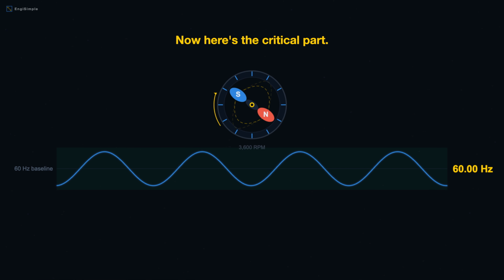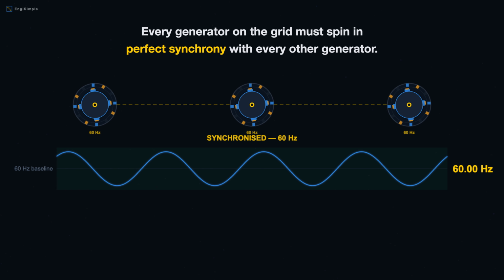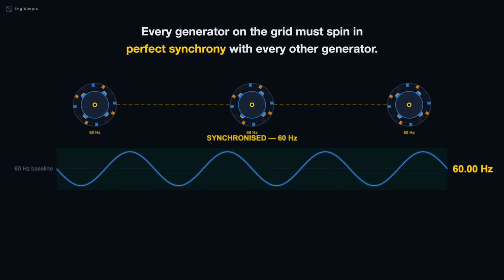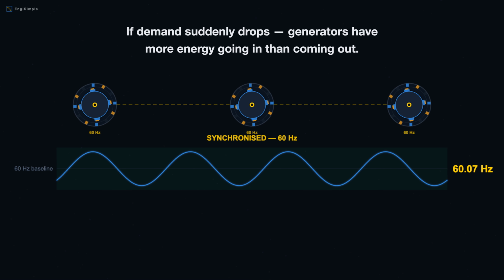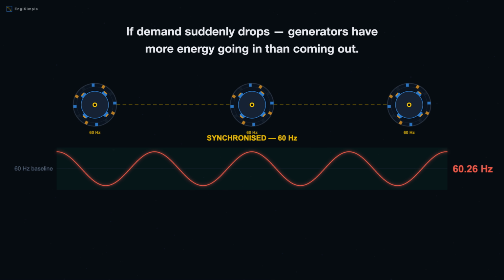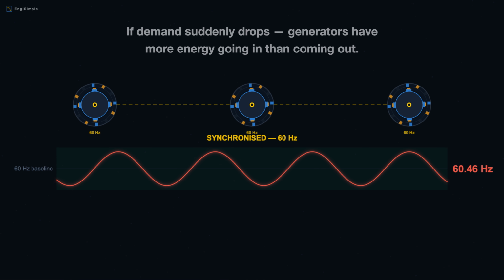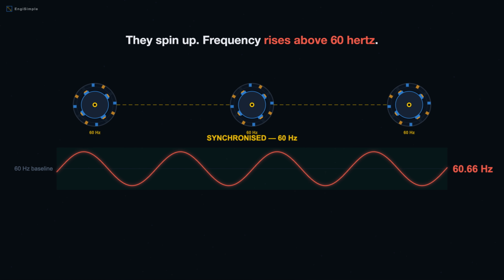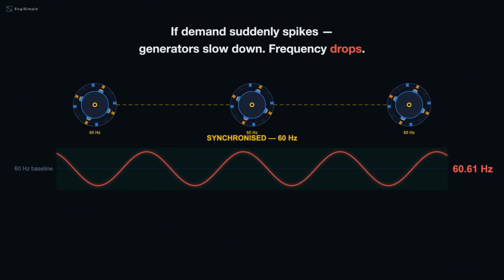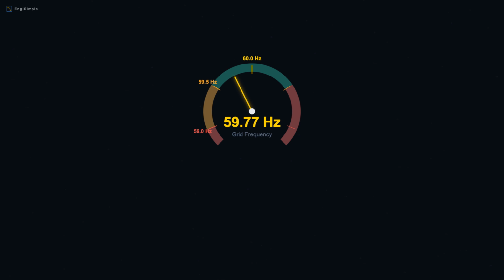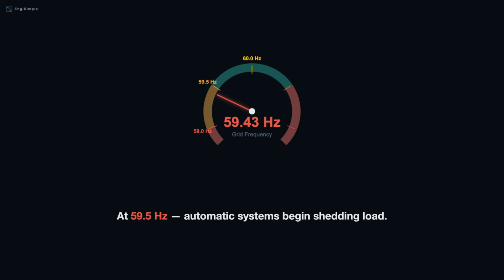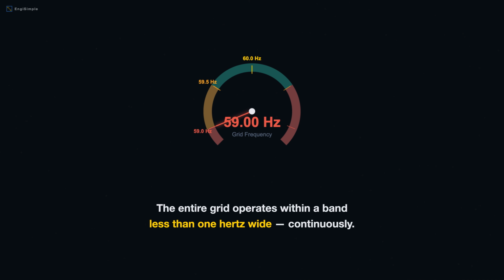Now here's the critical part. Every generator on the grid must spin in perfect synchrony with every other generator. If demand suddenly drops, because a big factory switches off, generators have more energy going in than coming out. They spin up. Frequency rises above 60 hertz. If demand suddenly spikes, generators slow down. Frequency drops. At 59.5 hertz, automatic systems begin shedding load. At 59 hertz, power plants start disconnecting to protect themselves. The entire grid operates within a band less than 1 hertz wide, continuously.